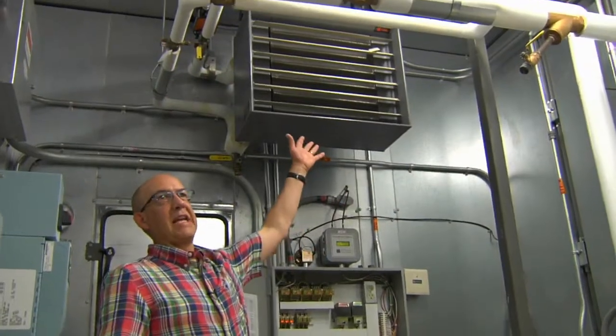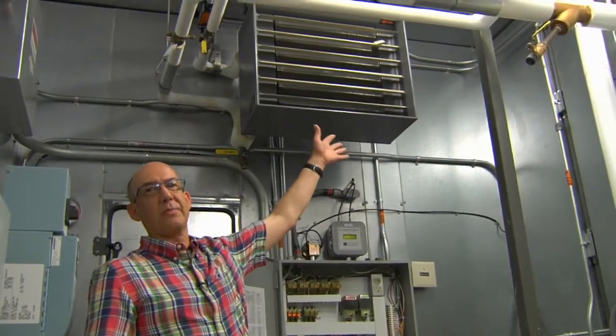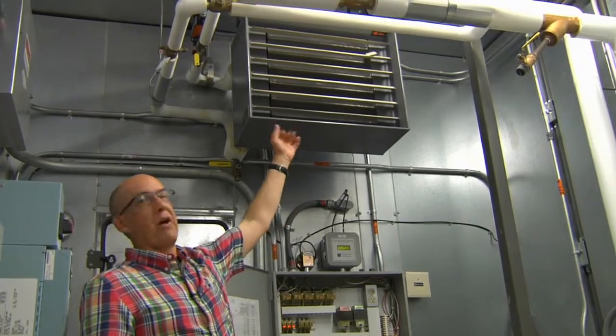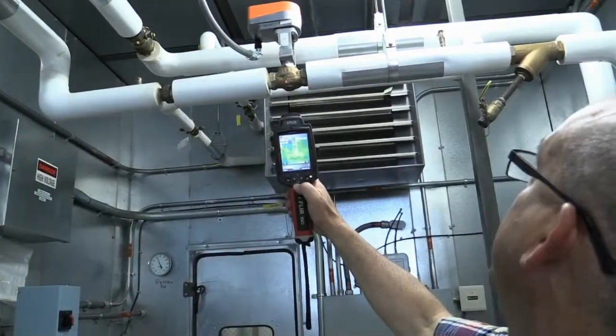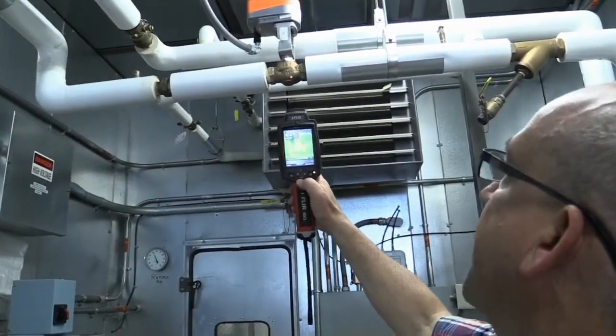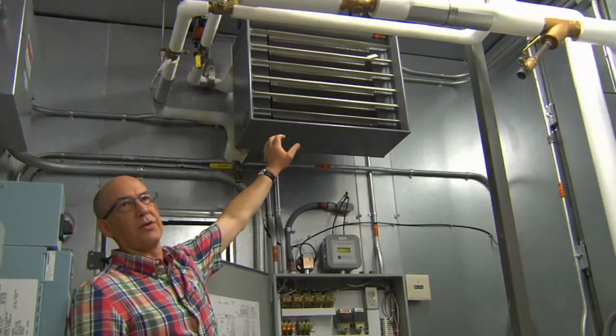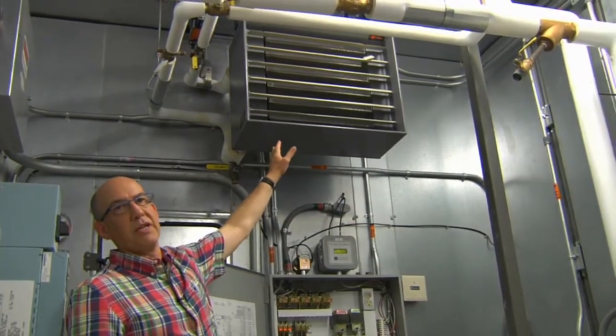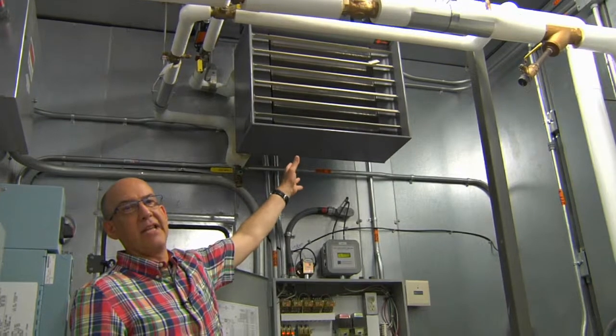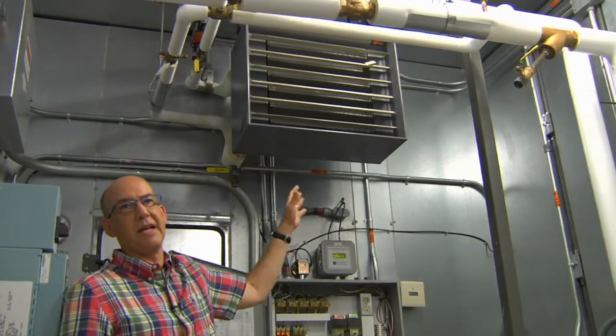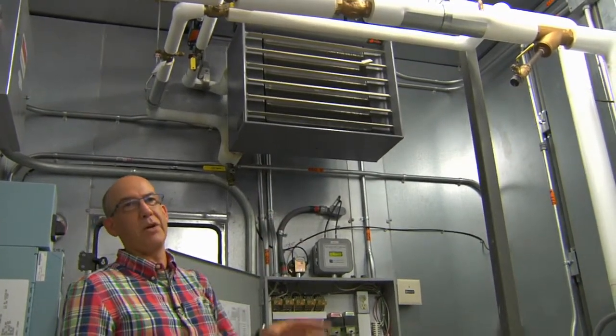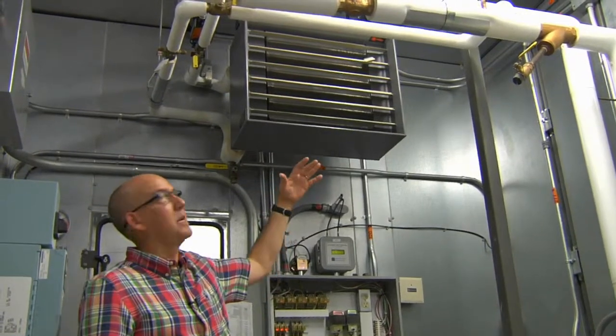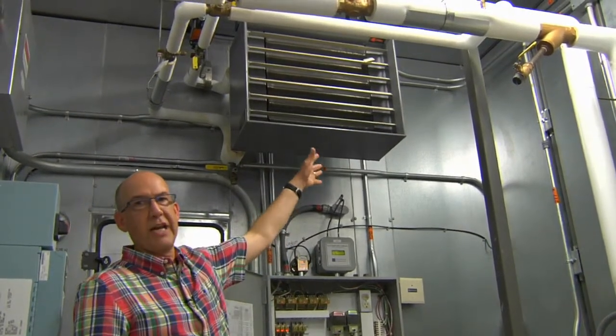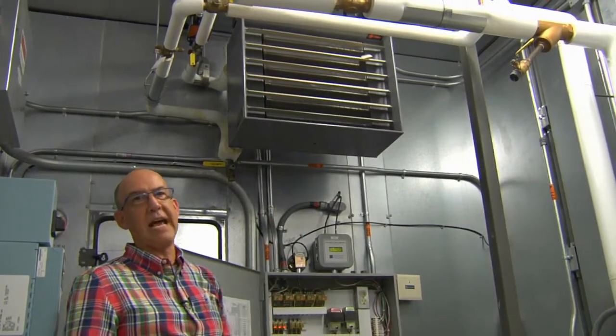And right above me here is a heating coil. These are common in mechanical spaces. In this fan room, we have a hot water coil. The good thing is we put an infrared camera on here, or we can put our hand up there on the coil surface. Either one will do to indicate that the coil is not heating the space. It's 95 degrees outside. It's about 85 in here. We don't need to be adding additional heat. So it's good to spot check your heating coils in the summertime, make sure they're not active.